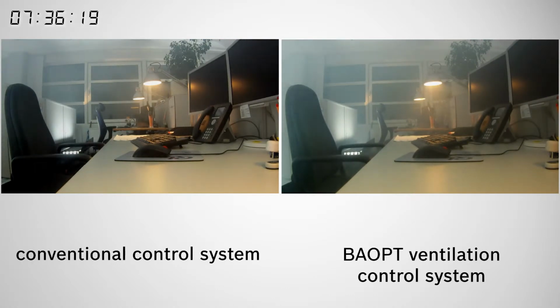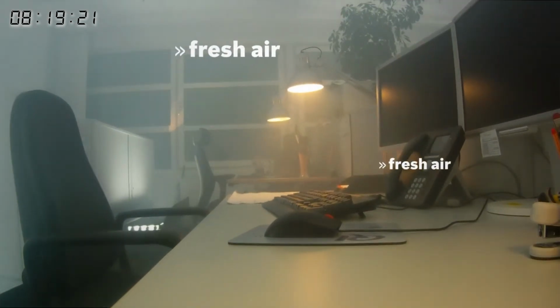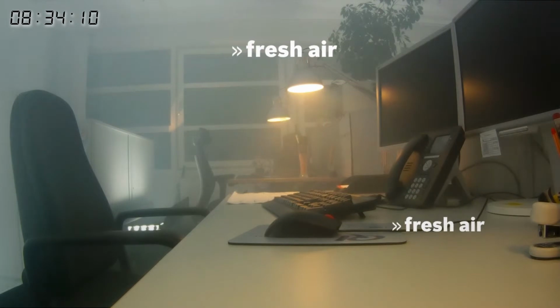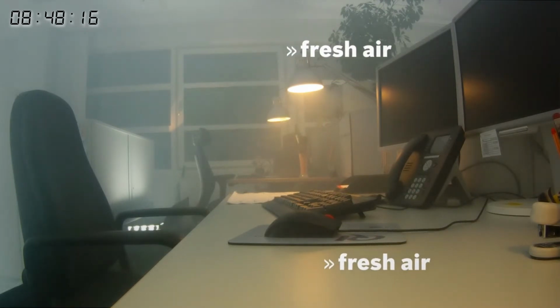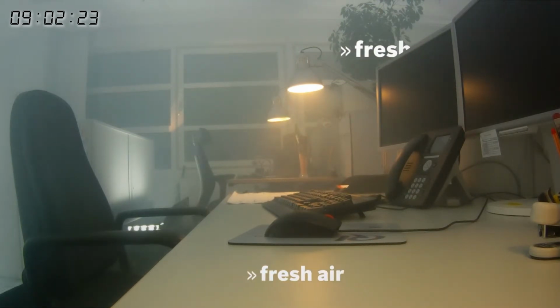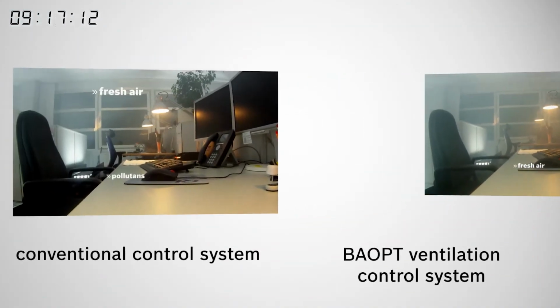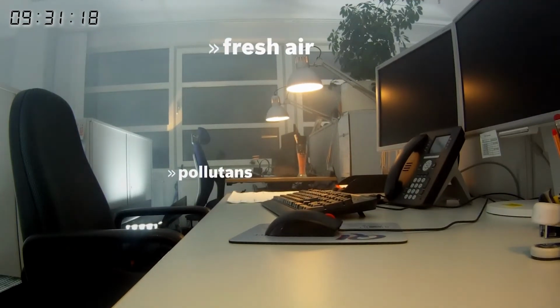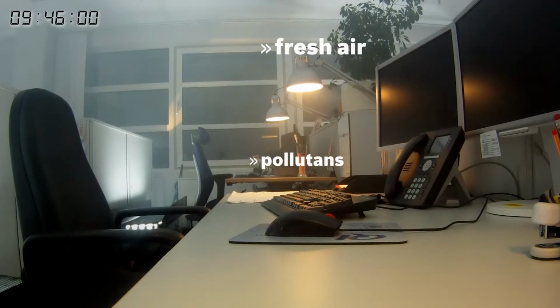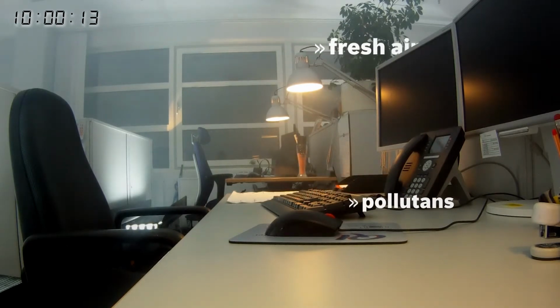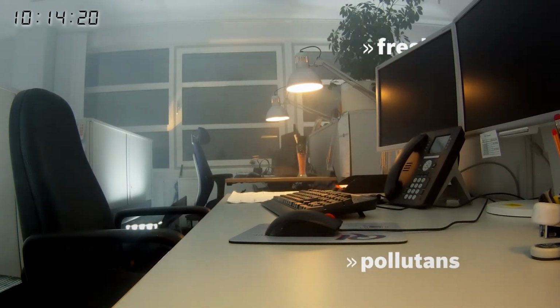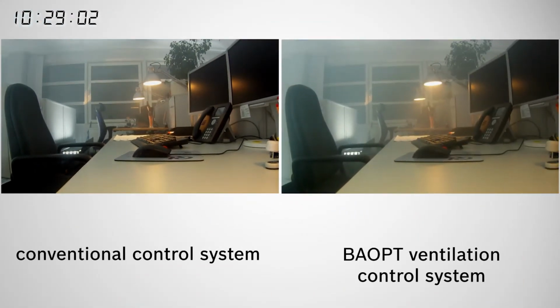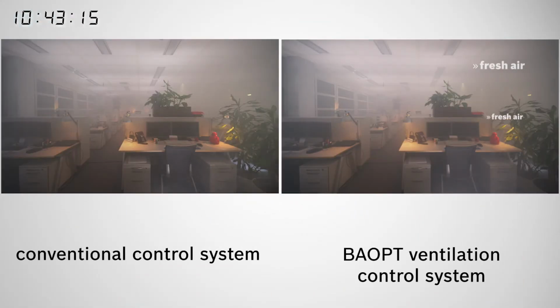After 7.5 minutes have passed, there is also a difference in terms of the lateral distribution. With the BAOPT system, the fresh air has already flowed evenly throughout the entire workplace. The conventional ventilation control system is clearly finding this difficult, struggling to overcome the obstacles of partitions in the room, and the fresh air accumulates near the ceiling. The BAOPT experiment on the right shows a completely ventilated office space with uniform airflow.